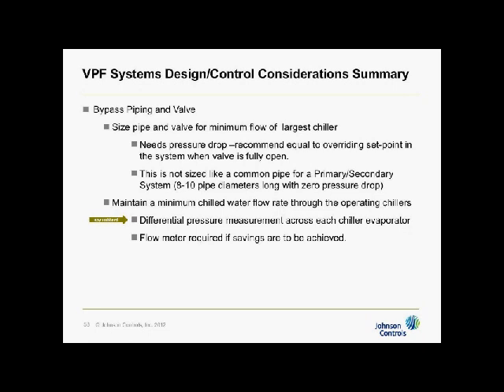Let me rephrase that again. When I'm at 3,000 GPM, I'm at 20 feet of pressure drop. But when I drop all the way down to 776 GPM, the minimum for this chiller, I'll be at 1.2. Now try to find some pressure sensor that you can control from that can monitor and measure that level. So you end up having to set your minimum flow much, much higher so you don't drop below dead bands and so on. So it is a much more accurate system to use the flow meters. You can go to lower flows so that when you are in bypass, you're not wasting as much energy.